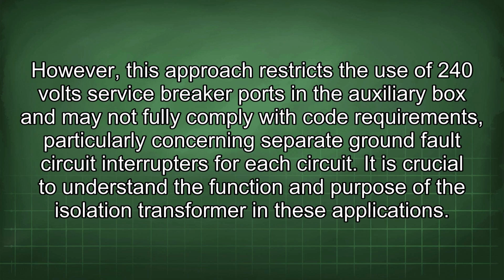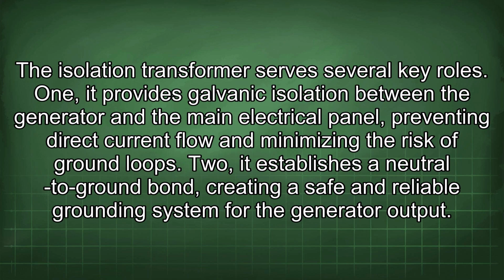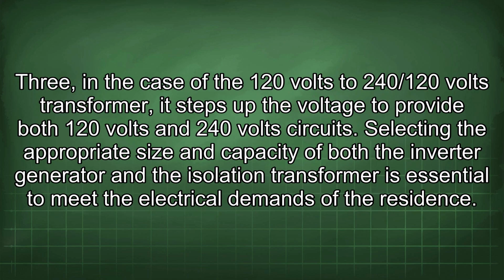It is crucial to understand the function and purpose of the isolation transformer in these applications. The isolation transformer serves several key roles. 1. It provides galvanic isolation between the generator and the main electrical panel, preventing direct current flow and minimizing the risk of ground loops. 2. It establishes a neutral to ground bond, creating a safe and reliable grounding system for the generator output. 3. In the case of the 120 volts to 240/120 volts transformer, it steps up the voltage to provide both 120 volts and 240 volt circuits.